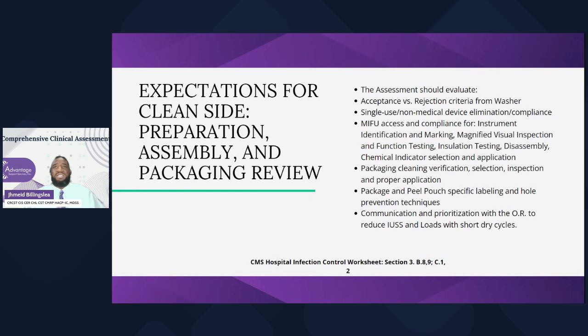IFU access, that's everywhere, right? And compliance for instrument identification and marking, when we're talking about tape, or laser etching, whatever method you're using. Do a risk evaluation on, is it worth it to have this tape or this dip, because when it starts going bad, it can be low hanging fruit for accreditation surveyors. That's one of those things you want to look at from the risk.